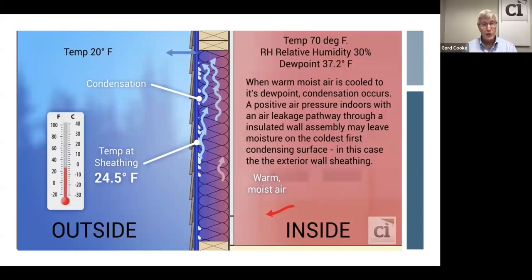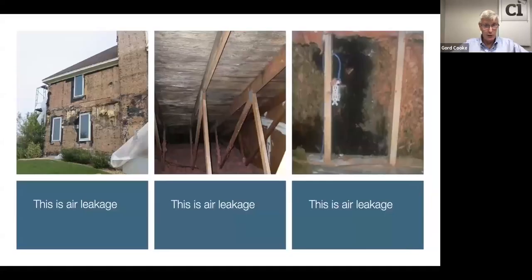Or three, you could add insulation to the first condensing surface, you could add insulation to the outside of the building. All worthwhile things to do. That is both things, air tightness and continuous insulation. But fundamentally, you don't want warm, moist air coming into contact with cold surfaces. So that's the code derivation, if you will.